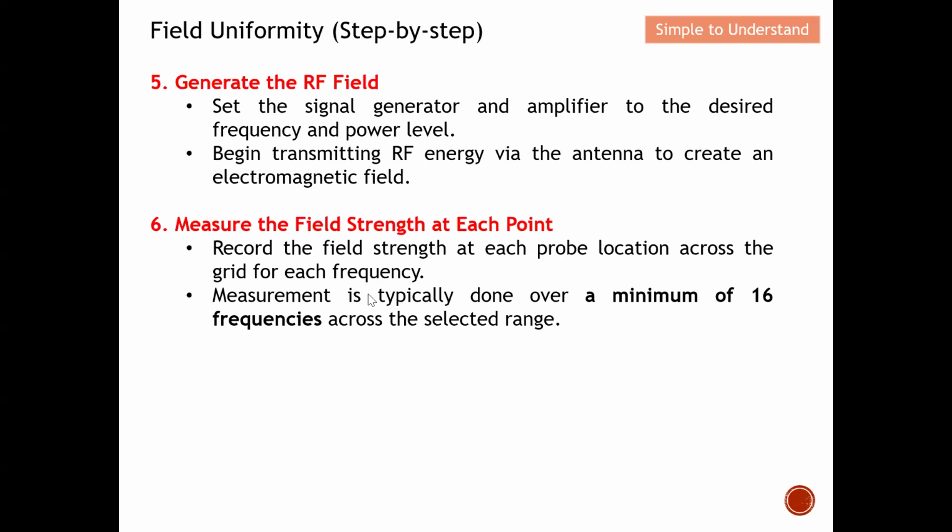Measurement is typically done over a minimum of 16 frequencies across the selected range. So basically, this is not fixed. In various situations, you actually need to do the measurement various times.